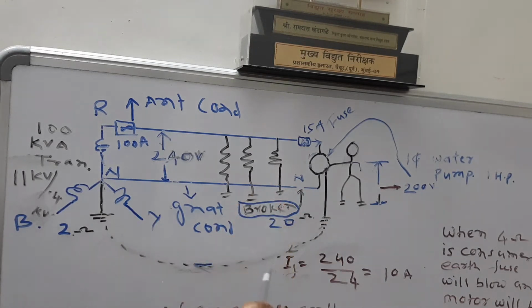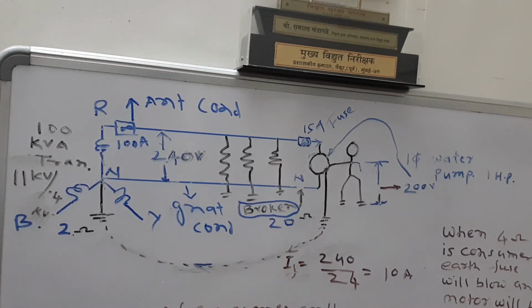Hence, we have to give much importance to consumer earthing and to distribution transformer neutral earthing. Generally, this neutral earthing should be as low as possible. It can even be less than 0.5 ohm, and generally it should be less than 1. But nowadays, because nobody is bothering about this earthing, these fuses do not blow. We cannot blame the earthing because we are not keeping it within value. If it is kept within value, definitely it will give results.